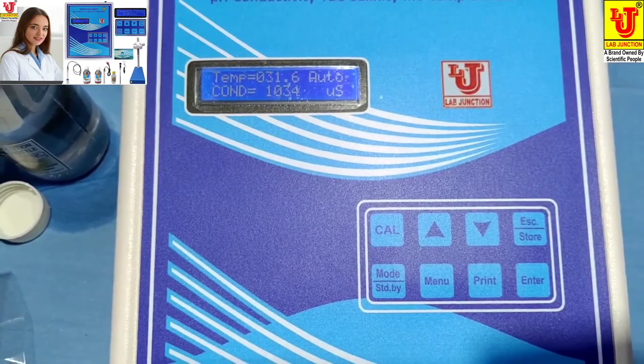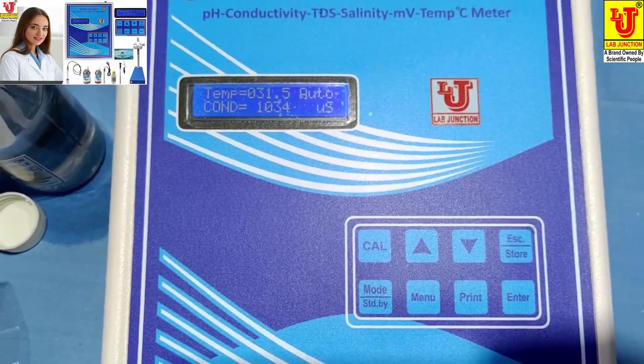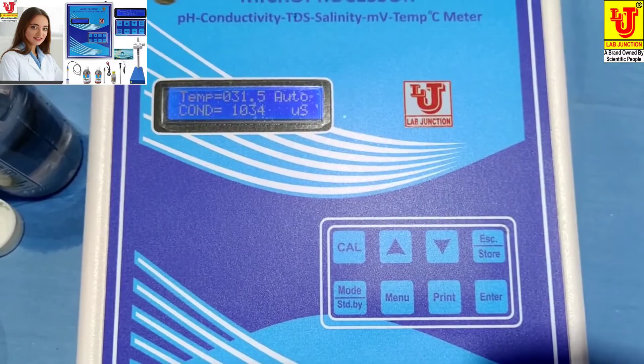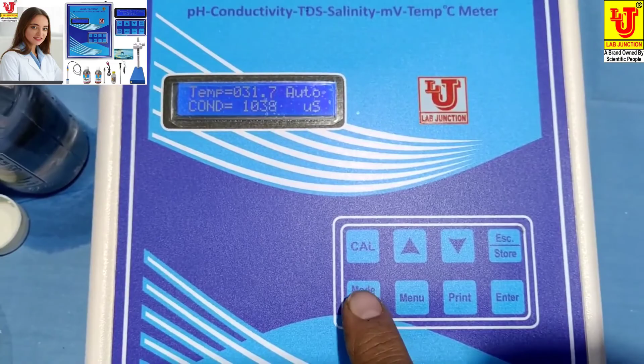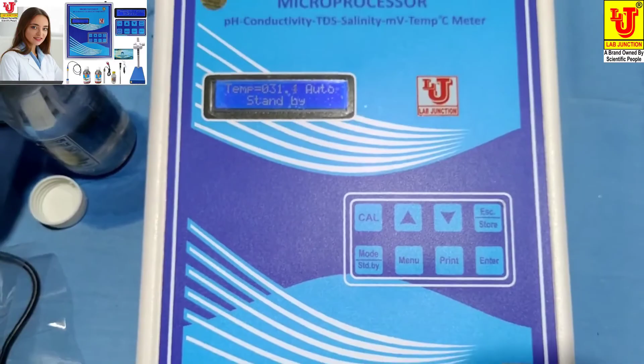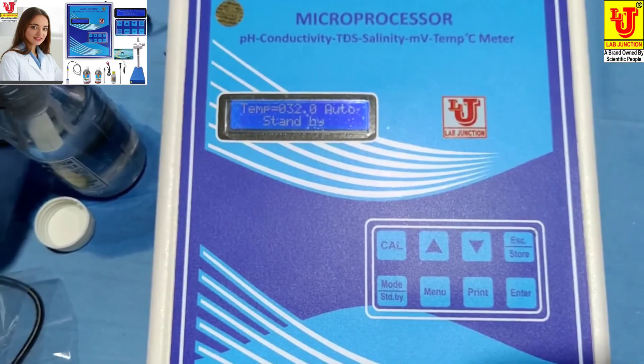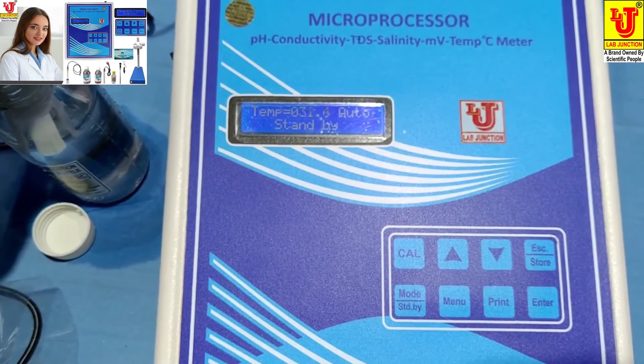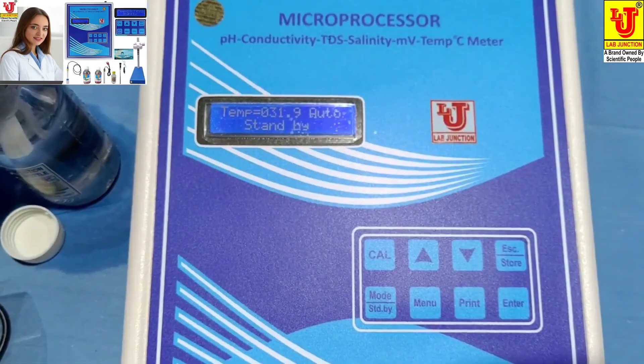This is my sample at this time, because conductivity changes according to temperature. Now this is the main display. If you have calibrated conductivity from the conductivity solution, then TDS and salinity are calibrated by default. No need to calibrate TDS and salinity if you have calibrated conductivity. If you calibrate conductivity, then conductivity, TDS, and salinity are calibrated at a single time. Thanks.